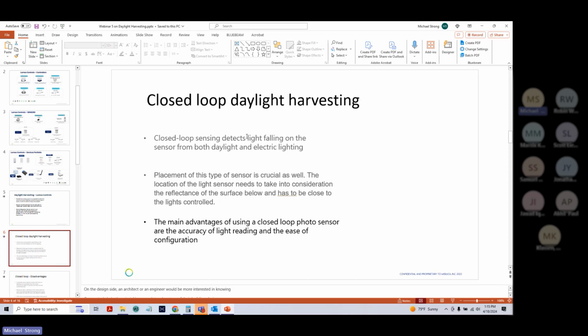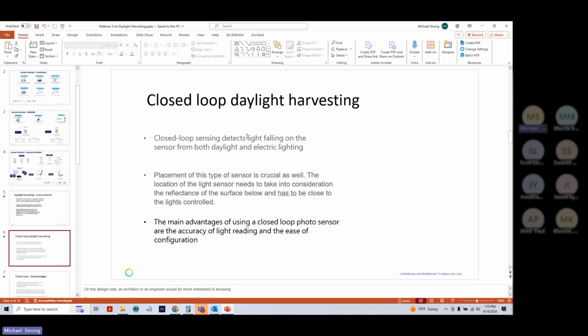And placement of this type of sensor, of course, is crucial. You want to take into consideration reflectances of the surfaces below, and they have to be close to the lights that we're controlling. So if you have a daylight zone and there are 4 lights in there, obviously you want your sensor to be in the center of those 4 lights, or at least close to the light engines, as well as near the window, so they can capture both segments relatively easily, and the combination of the two, so that we can set figures like 24-foot candle.